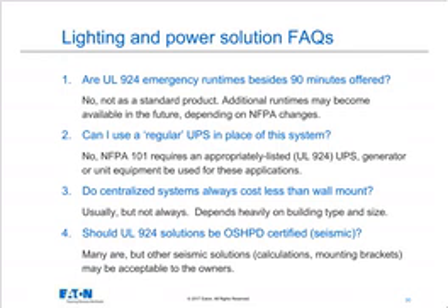Can I use a regular data center UPS in place of a UL 924 system? There's another couple of things that are different besides just the longer battery. The controls of the UPS and the bypass controls in particular need to be designed so that the user cannot inadvertently transfer the UPS to plain utility bypass and then forget to put the UPS back online. Because if they do that, then of course a subsequent power outage will result in all lights going off. So locks and barriers are put in place so that the UPS cannot be inadvertently left on bypass. You know, somebody comes in for maintenance and forgets to put the UPS back online when they're done.